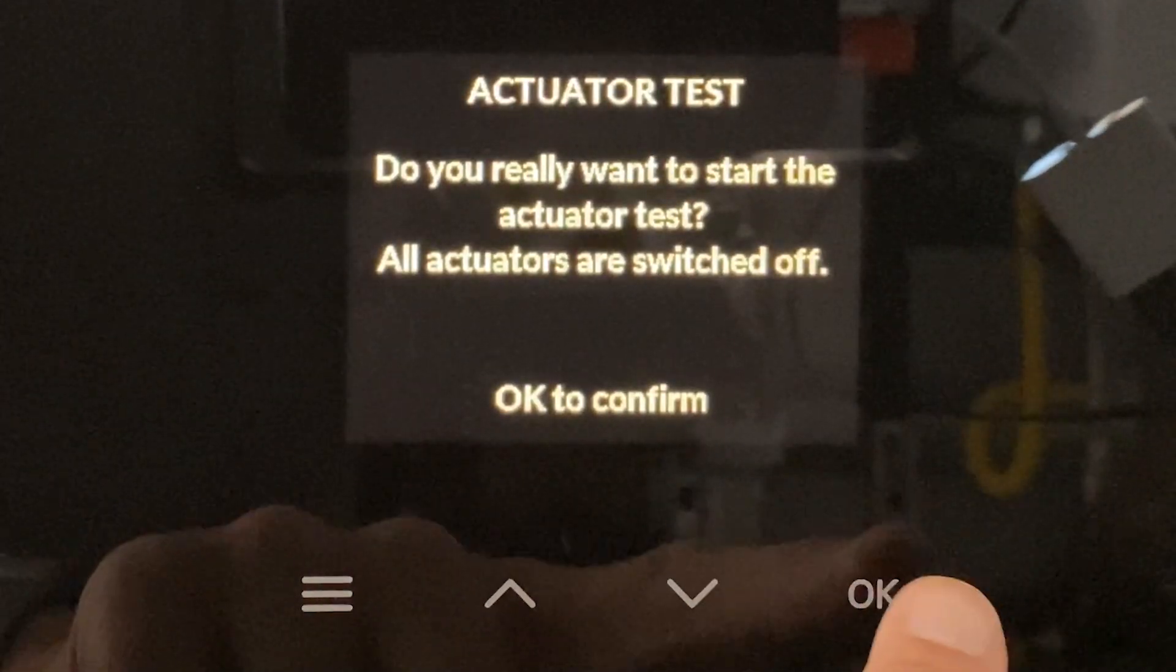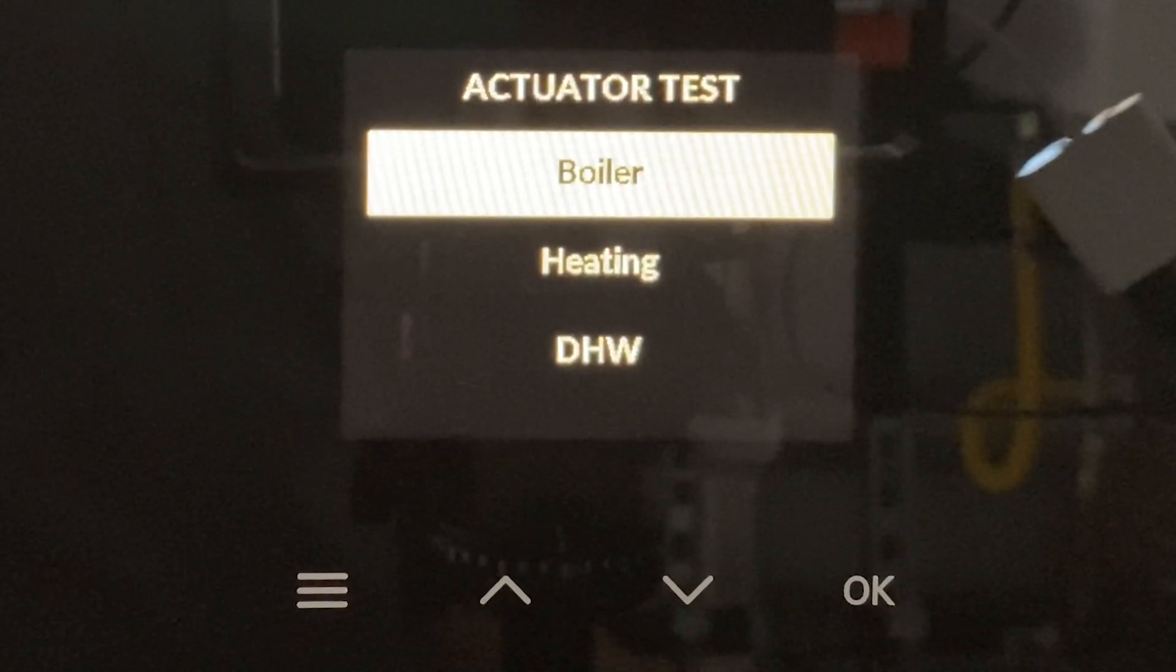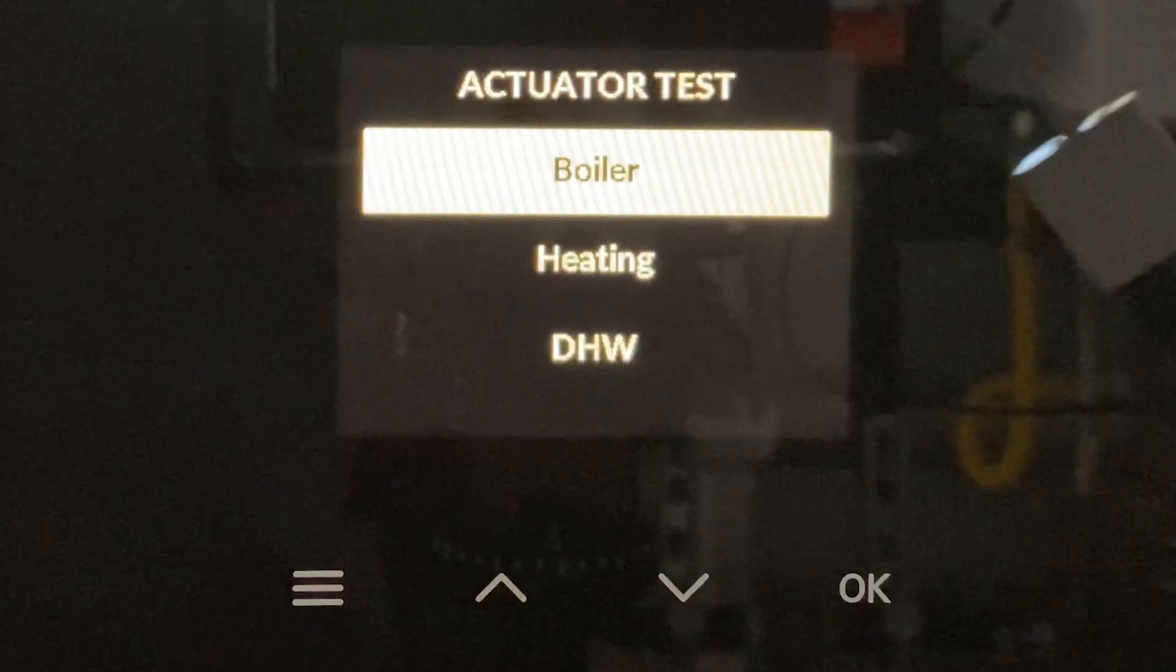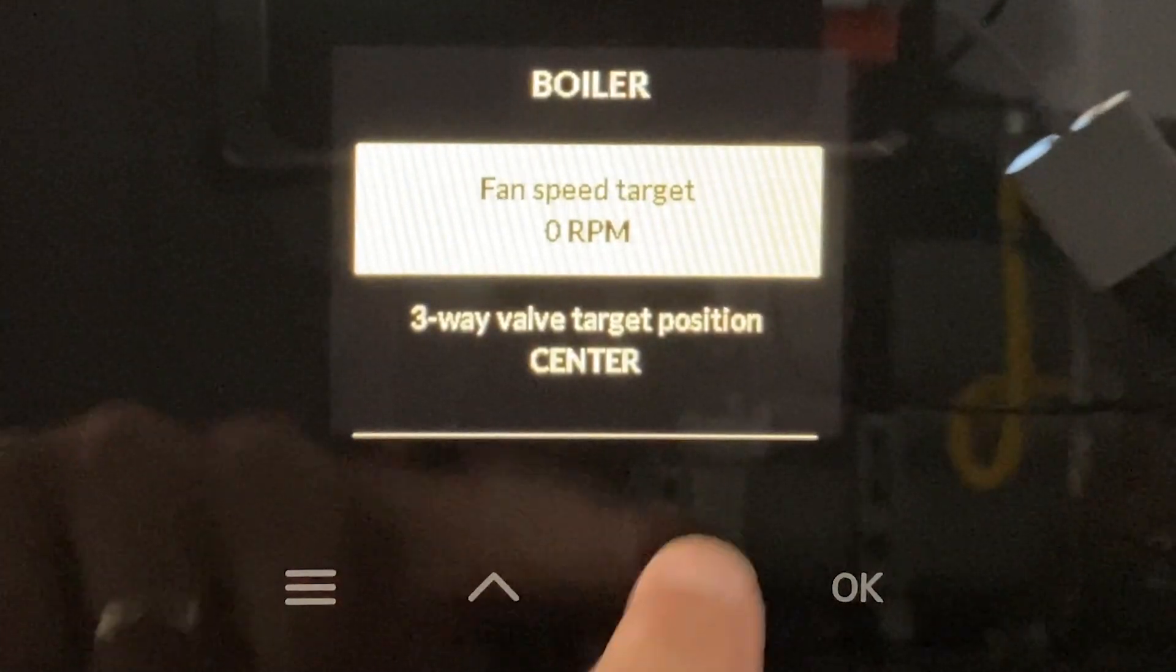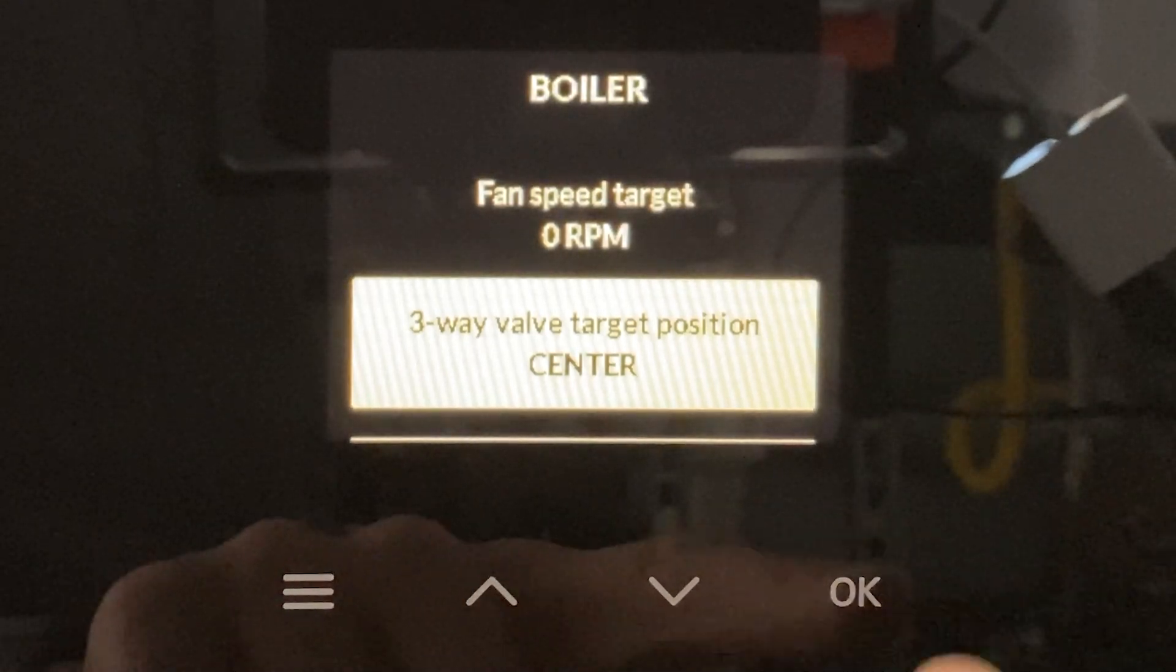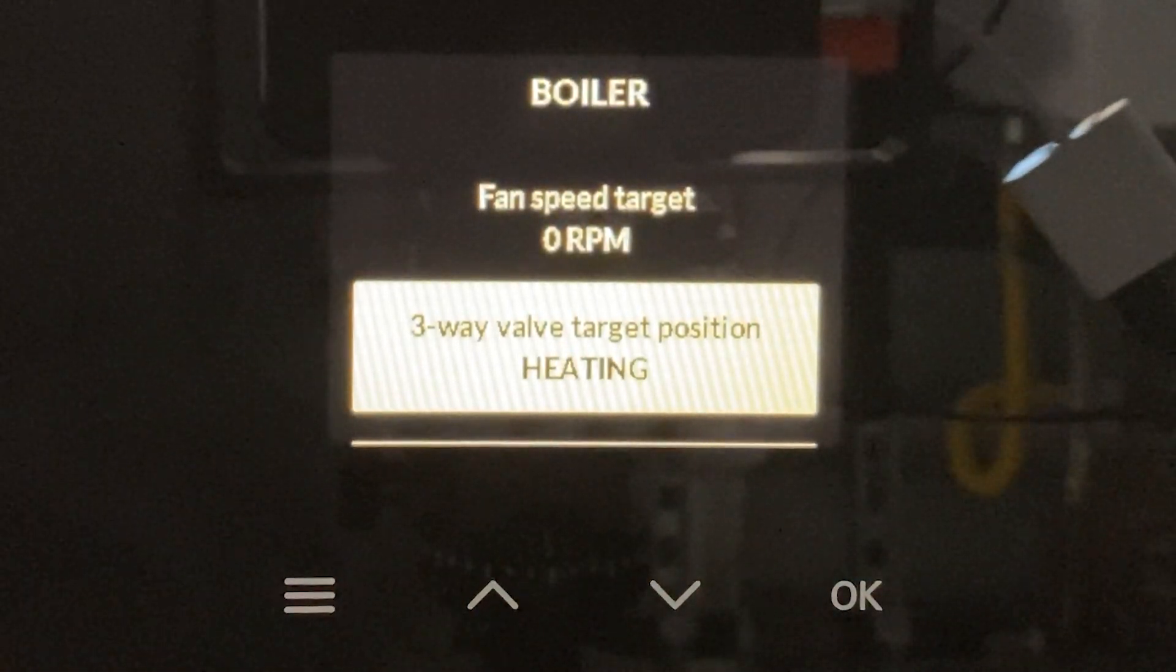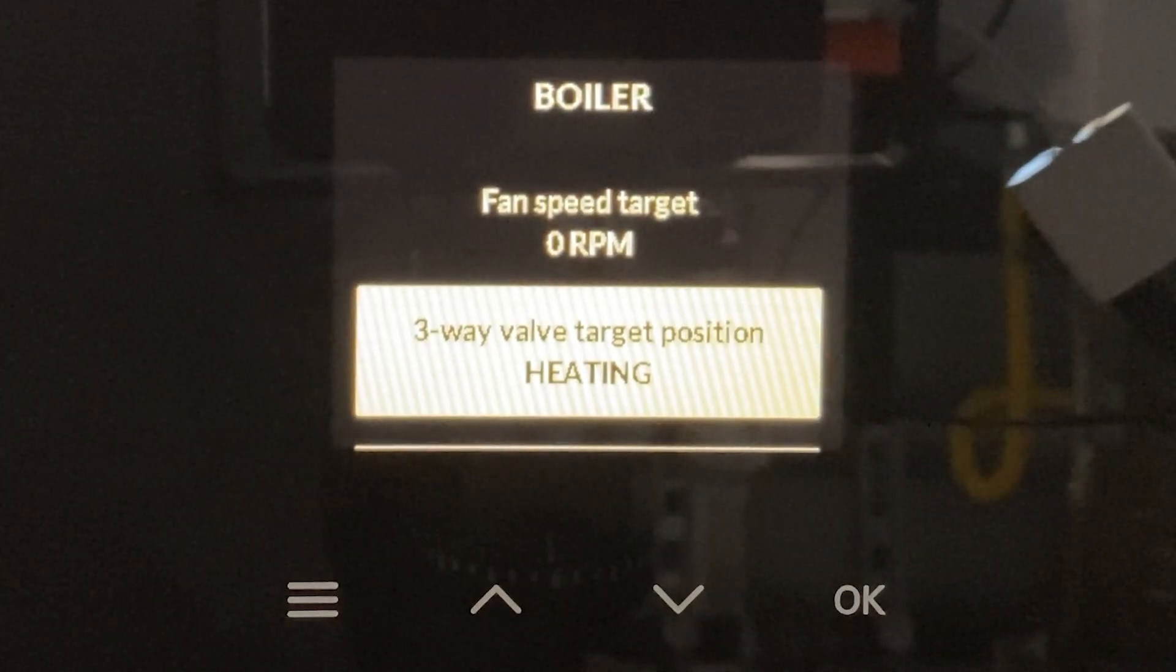Now there are three sub menus in the actuator test. All three of these contain the actuator test to move the diverting valve, so you can choose any one of the three. I've highlighted three-way valve target position and simply by pressing the OK button I can toggle the valve or essentially actuate the valve between its three positions.